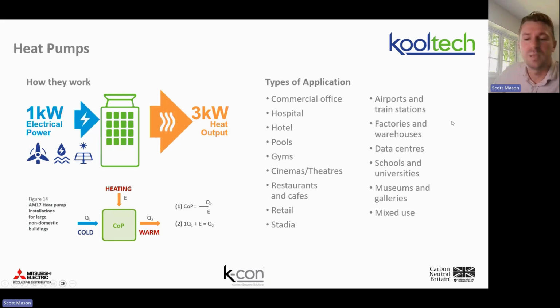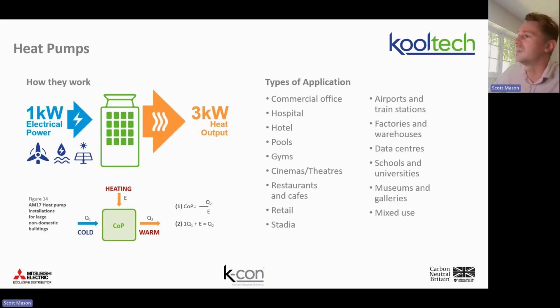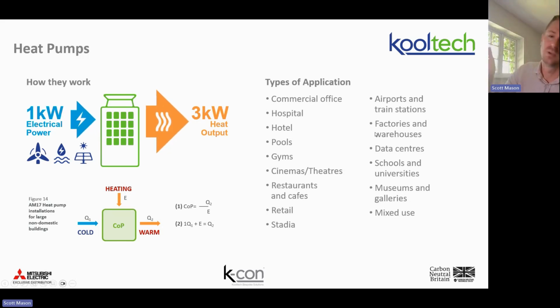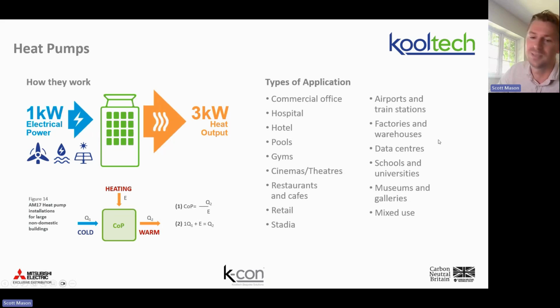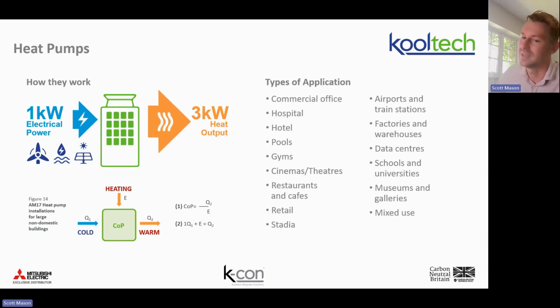Well, the other barrier is probably going to be flow temperature. So your historic retrofit, realistically, you've got a boiler working on 80–60. We want to flow at 80 degrees to the building. We want to return at 60 degrees. We've got a 20-degree delta T across the building. Boilers are comfortable doing that. It won't condense, but it doesn't really matter if it's an existing system. It does matter from a carbon point of view, of course it does. But on older buildings, if it's not condensing, it just means that your efficiency is lower and your gas running cost is slightly higher. Later buildings went to 70–50, so they got underneath that condensing boundary, but even then 70 is a stretch for most technology, which we'll discover very shortly.